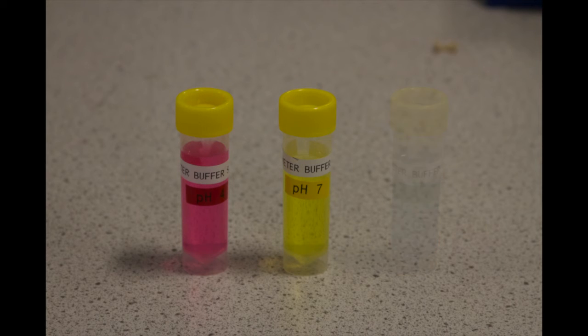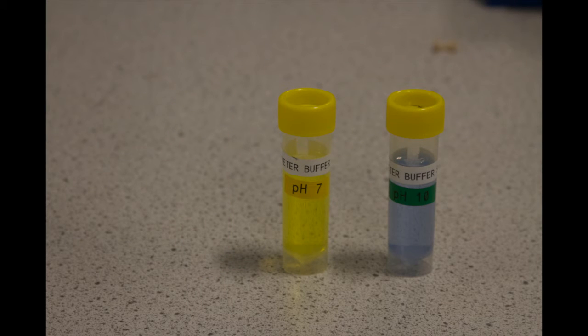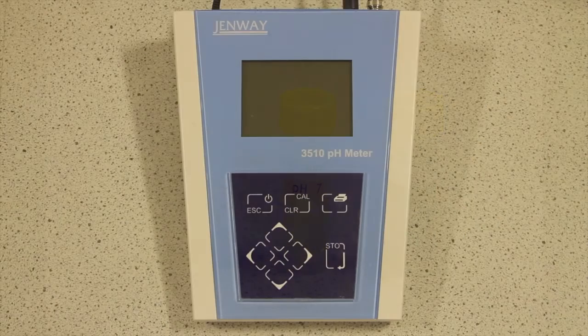There are 3 different solutions used to calibrate the pH meter before use. A pH 4 solution, coloured pink-red, a pH 7 solution, coloured yellow, and a pH 10 solution, coloured blue. The purpose of these solutions is to allow the pH meter to be calibrated across the pH range being measured. If you were wanting to measure the pH of an acidic solution, you would calibrate using the pH 7 and the pH 4 solutions. If you were wanting to measure the pH of an alkaline solution, you would calibrate using the pH 7 and pH 10 solutions.